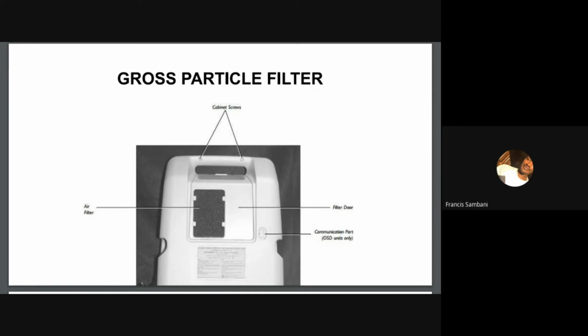We should know that even a small increase in the oxygen level, up to 24%, can create a fire hazard. An oxygen concentrator has the ability to go up to 95.6%. So you can see that the risk is much higher when you're using an oxygen concentrator, because 24% is not far away from 21%, and room air contains 21% oxygen. That's why you're supposed to take caution when you're using this equipment.